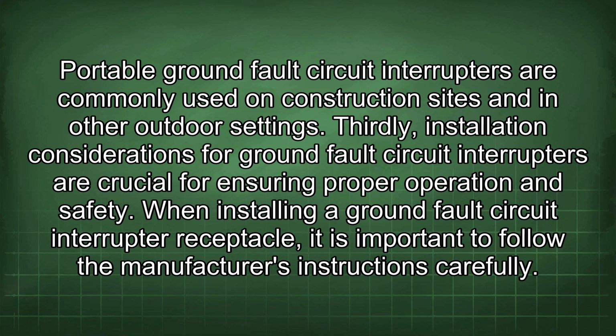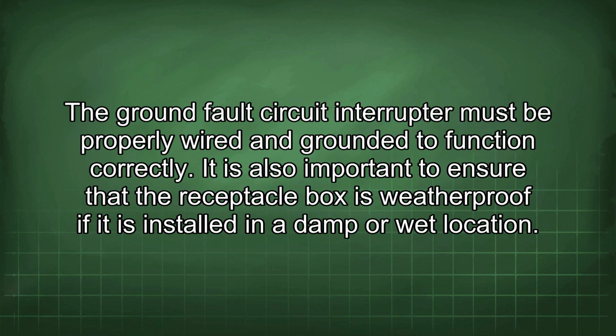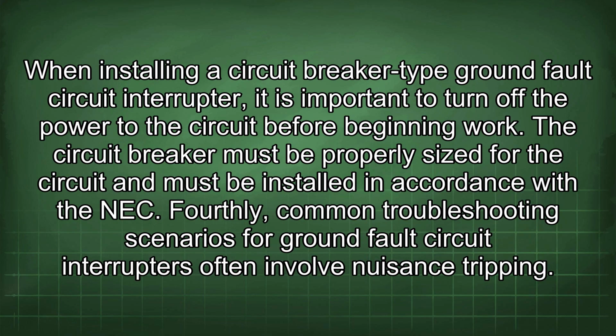Thirdly, installation considerations for ground fault circuit interrupters are crucial for ensuring proper operation and safety. When installing a ground fault circuit interrupter receptacle, it is important to follow the manufacturer's instructions carefully. The ground fault circuit interrupter must be properly wired and grounded to function correctly. It is also important to ensure that the receptacle box is weatherproof if it is installed in a damp or wet location. When installing a circuit breaker type ground fault circuit interrupter, it is important to turn off the power to the circuit before beginning work. The circuit breaker must be properly sized for the circuit and must be installed in accordance with the NEC.